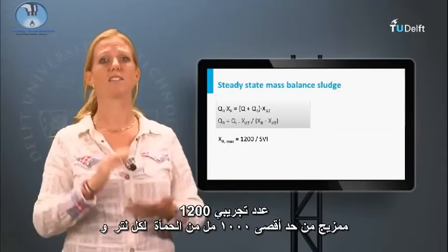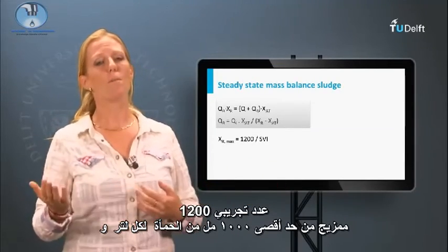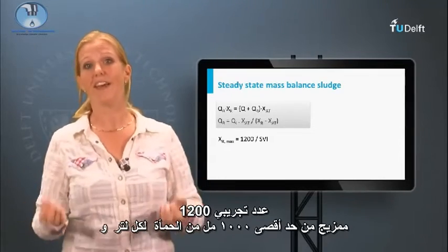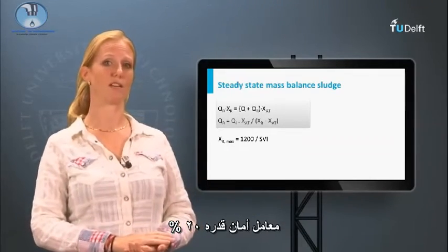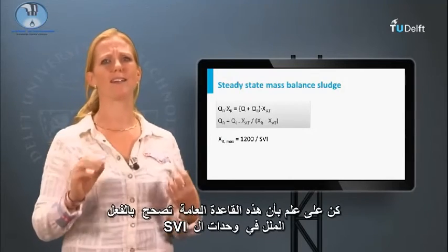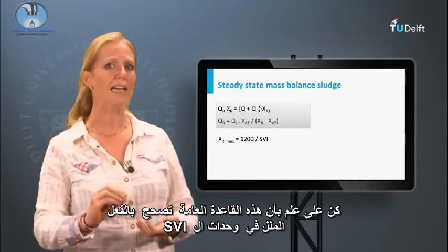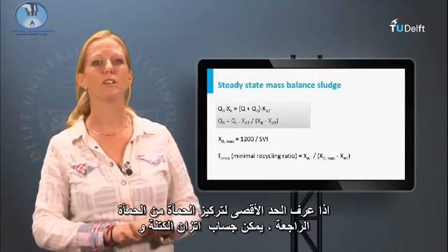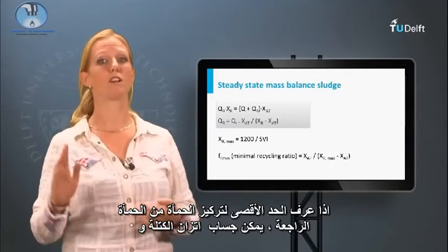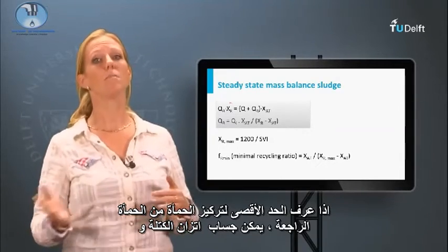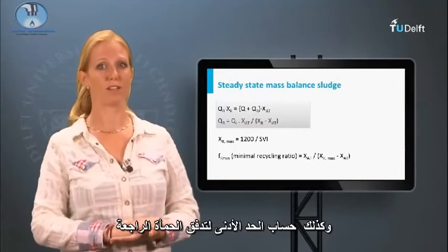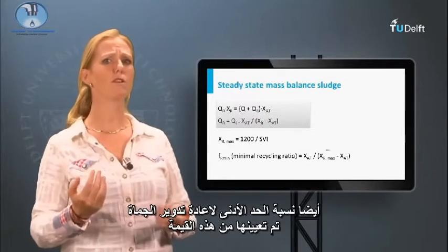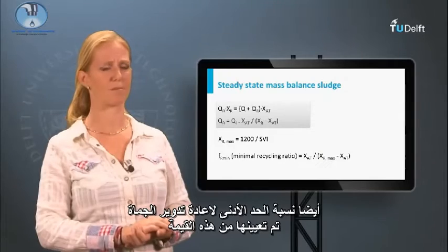1200 is an empirical number, a combination of a maximum of 1000 milliliters sludge per liter and a safety factor of 20 percent. Be aware that this rule of thumb already corrects for the milliliters in the SVI unit. If a maximum sludge concentration of the sludge recycle is found, the mass balance and the minimum return sludge flow can be calculated. Also the minimum recycle ratio is set by this value.